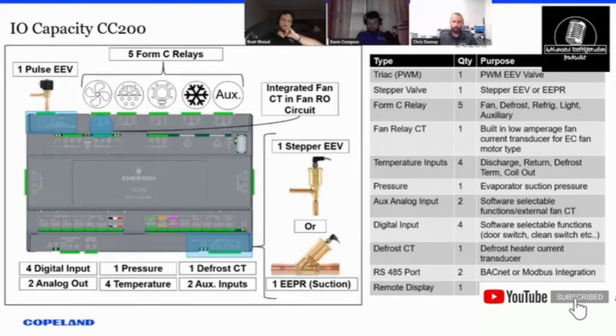So if you hook up the fan circuit on the cases directly, we are able to monitor the amperage of the fan circuit. And we've tested this on multiple motor types, and the ECM motor type was a little tricky in the beginning, but we tested on ECMs to be accurate all the way down to sub 0.2 amps, like down to 150 milliamps in that range.